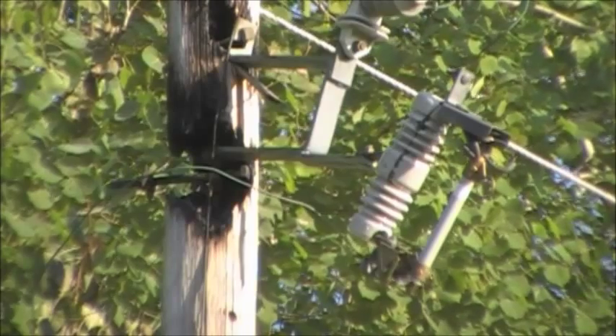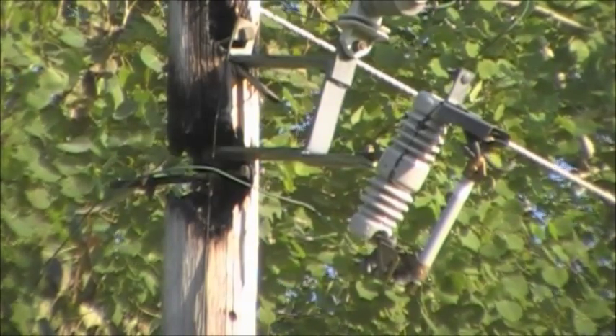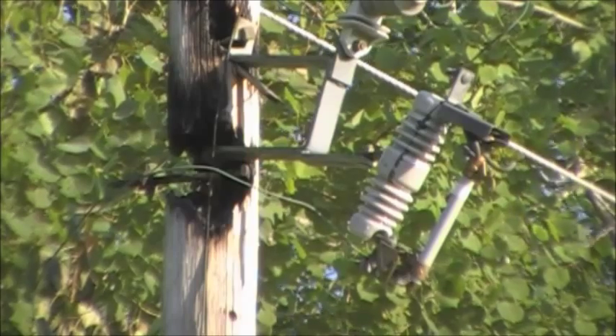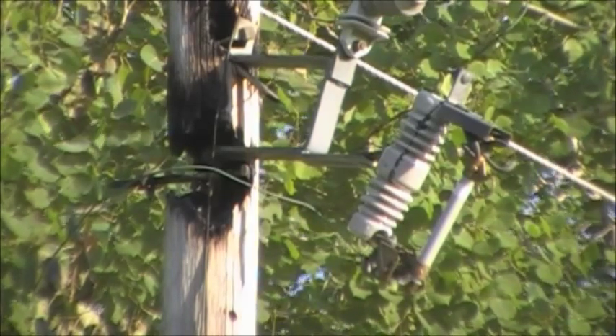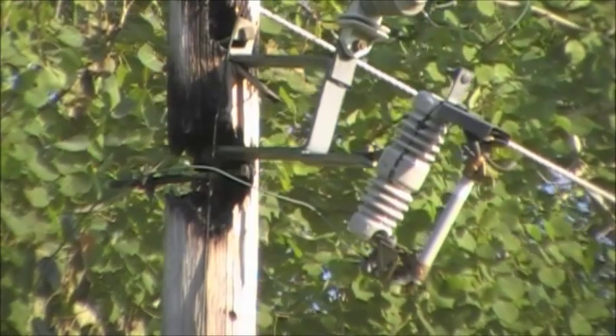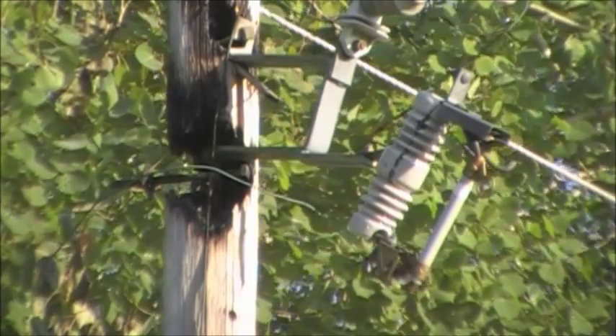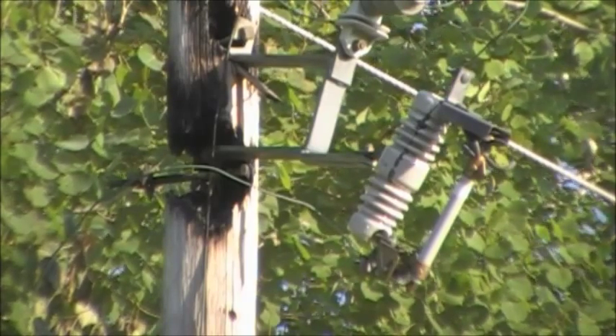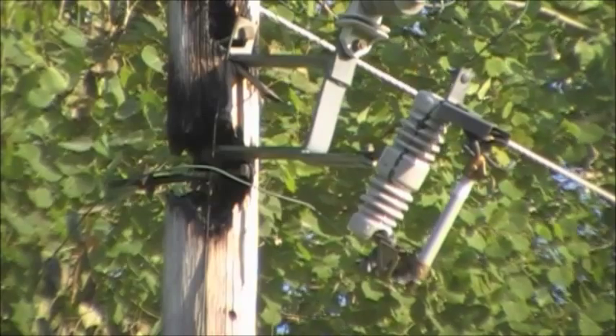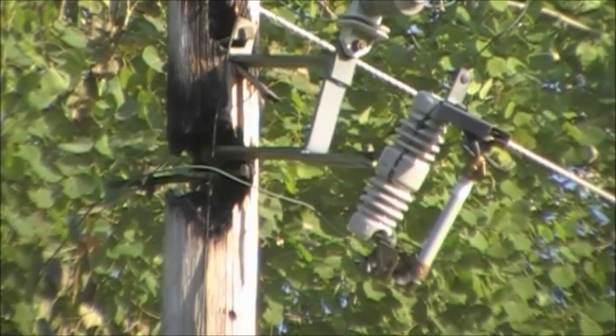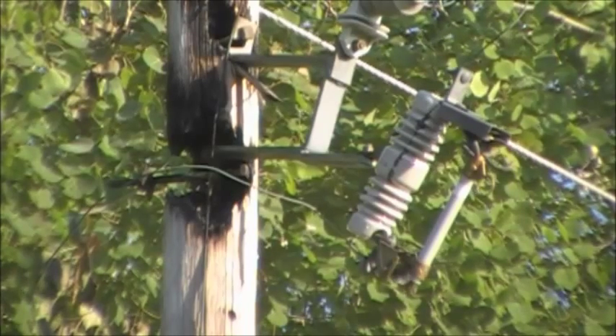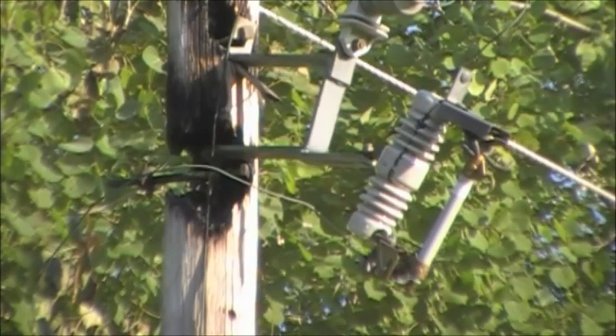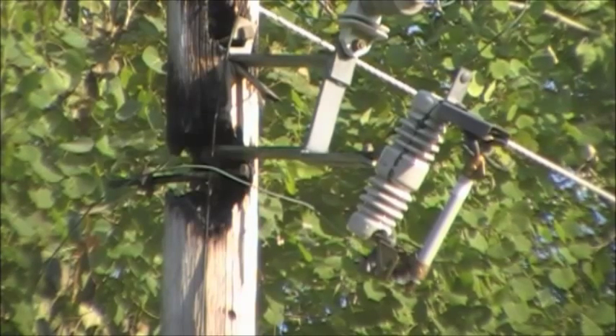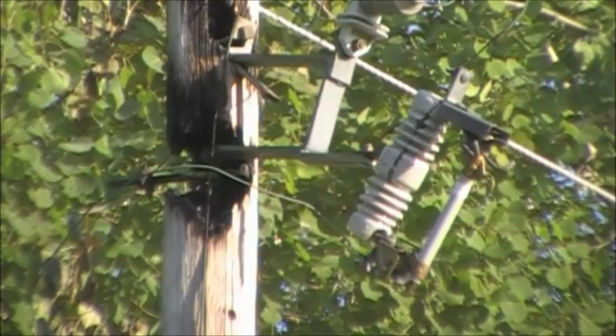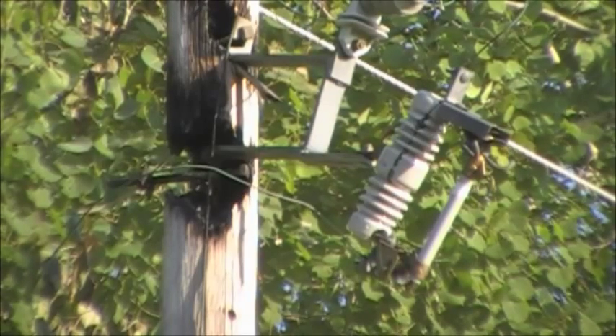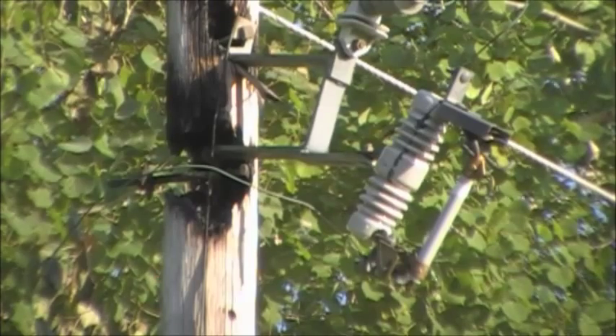Okay, I'm going to get a couple other quick angles here just to get a good look at it. If you notice that insulator on a diagonal there, that's where the knife switch is. And you see that black line on the insulator. That very likely is a crack in that insulator, and has compromised the insulator, allowing some current to flow through to the supporting hardware, which when the pole is wet, shorts it to ground and heats it up very hot and burns the pole in half. There's not much holding that upper part of the pole up right now. Maybe 20% of the pole, if that much, is left.